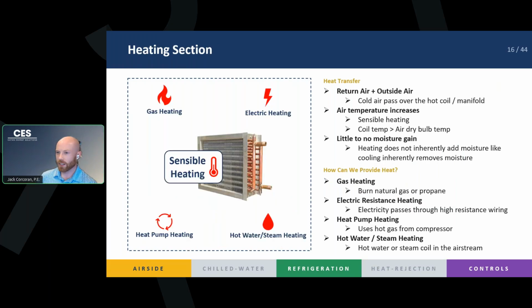And the next section is our heating section, right? We followed our air through our outside air dampers, our return dampers, went through the filters, went through our cooling coil. If we're in heating season, that cooling coil is off, right? And we're going to have this heating section on. It's the same deal, right? We're going to have our outside air and our return air, which is cold this time, pass over the coil or the manifold or any form of heat, right? So we're providing our heat. These icons say it all, right? We can use gas heating, we can use electric heating, we can use heat pump heating, or hot water or steam heating. Oftentimes, our packaged rooftop units are defined by the type of heat they use.